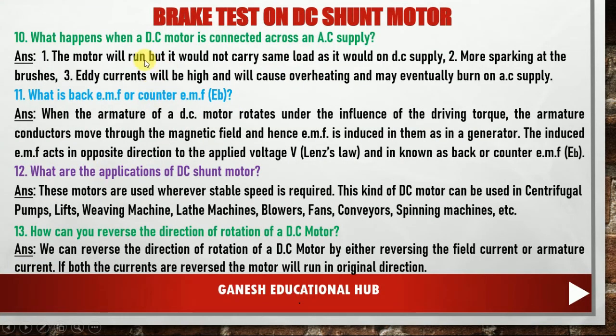Tenth question. What happens when a DC motor is connected across an AC supply? Actually, a DC motor is always connected to a DC supply, but if it is connected to an AC supply, what happens? First point, the motor will run, but it would not carry the same load as it would on DC supply. Second, more sparking at the brushes. Third, eddy currents will be high and will cause overheating, and the motor may eventually burn on AC supply.